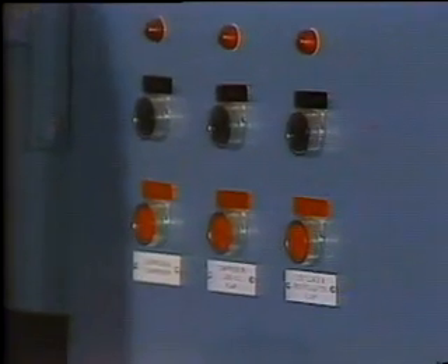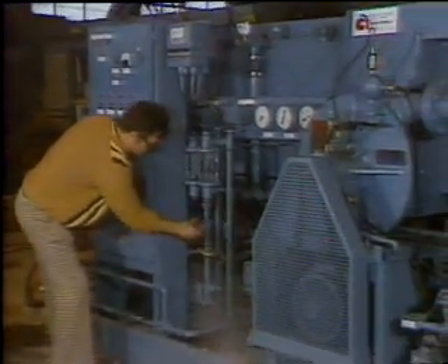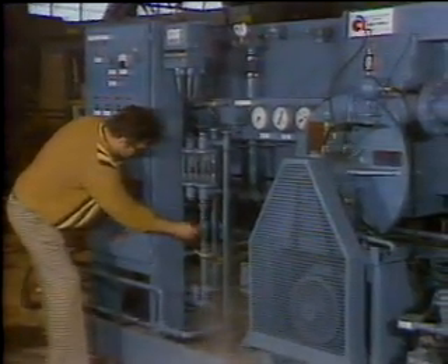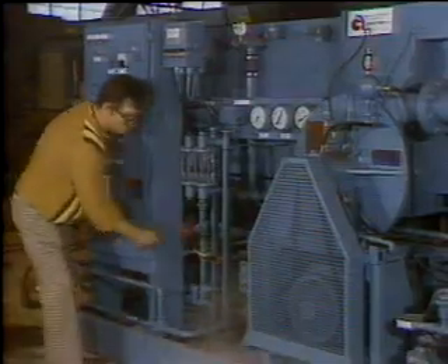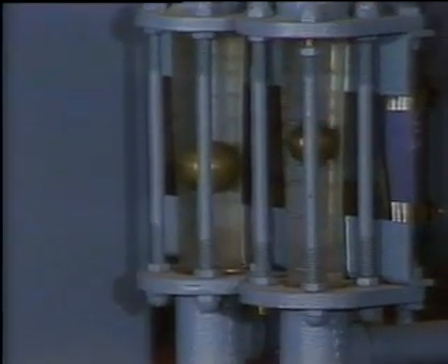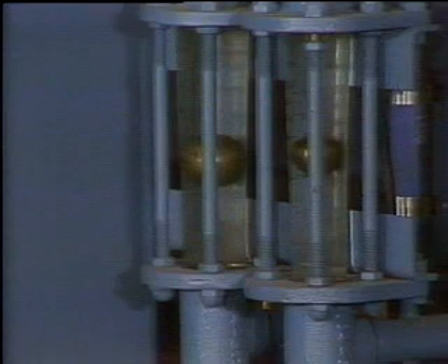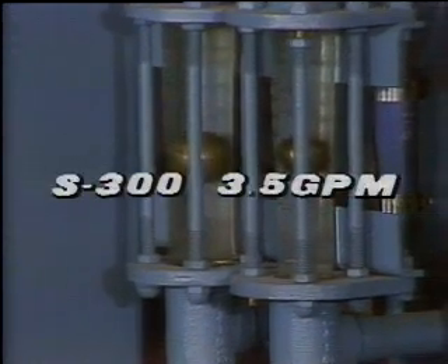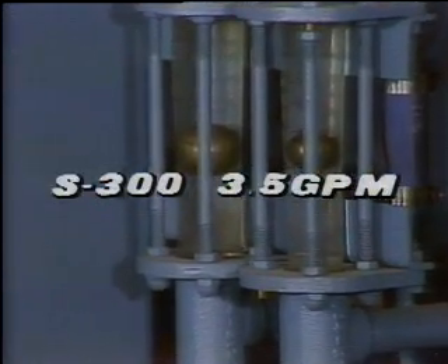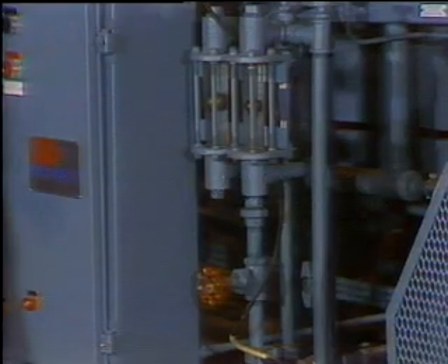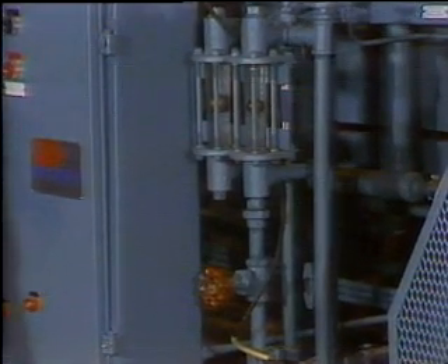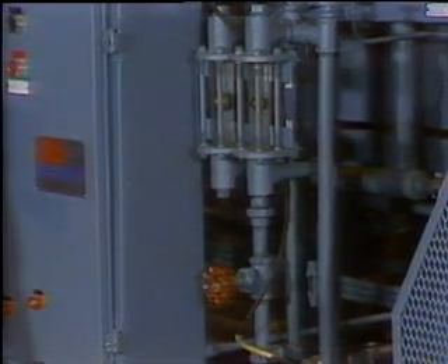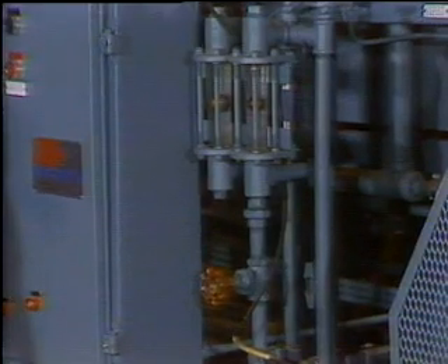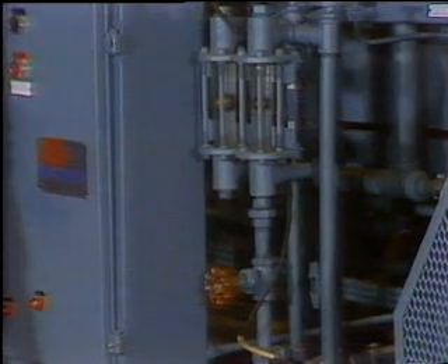Okay, after 2 minutes, start the compressor and open the distillate shutoff valve fully. Now, slowly open the feed water control valve to flow at about 1/3 of the plant's distillate capacity. On this S300, that would be about 3.5 gallons per minute. If too much cold water is introduced into the system too quickly, it'll cause the unit to cool down too rapidly and shut down, so be careful not to introduce too much cold water too fast.